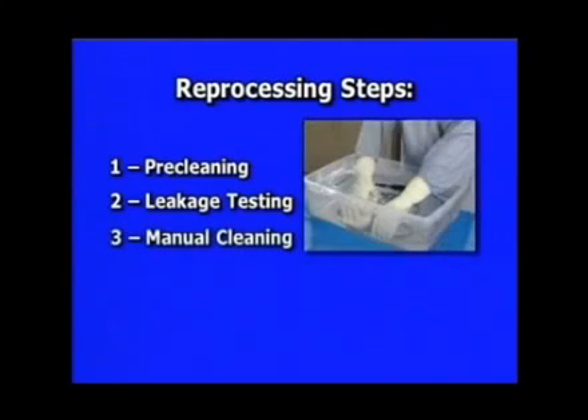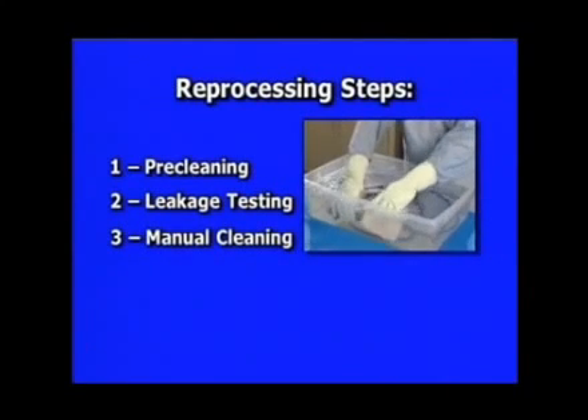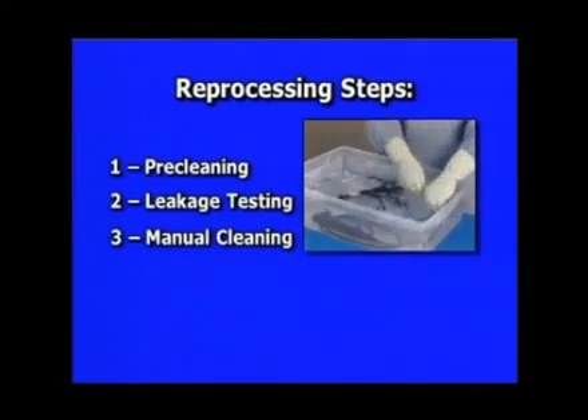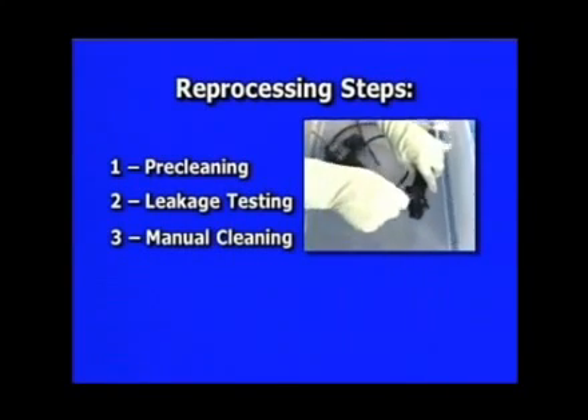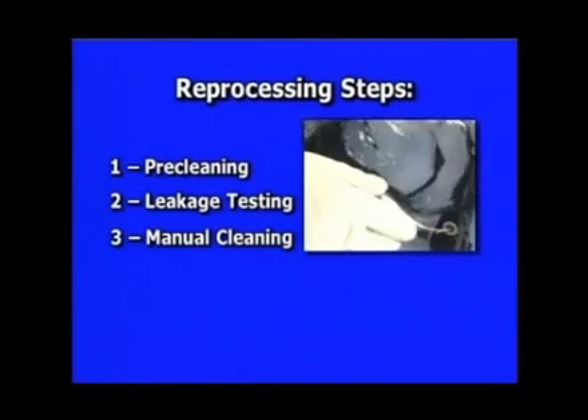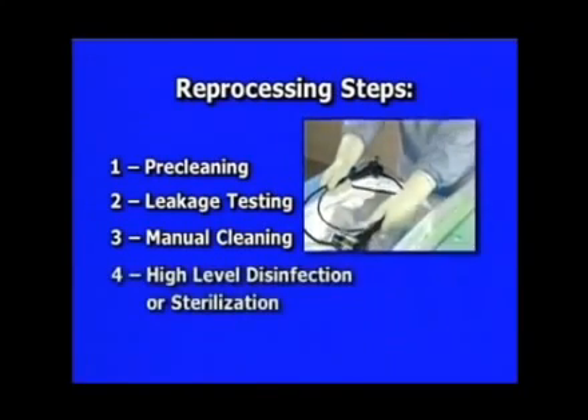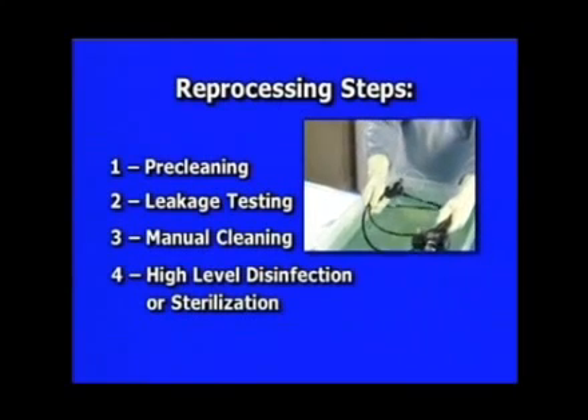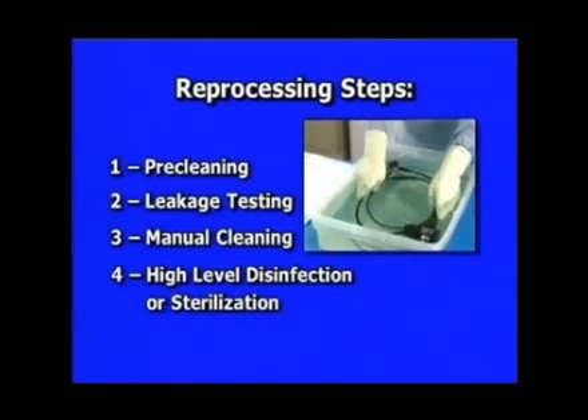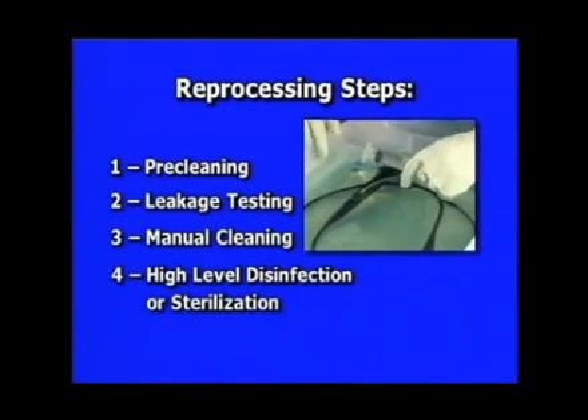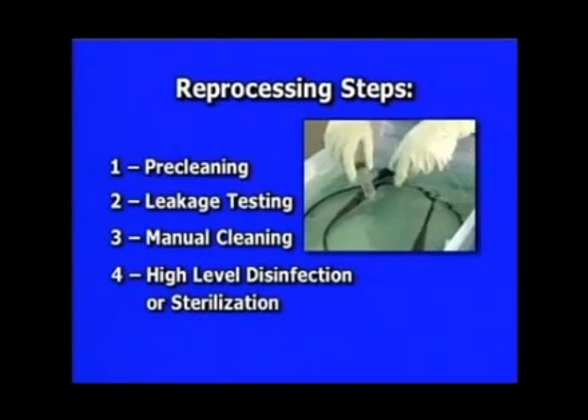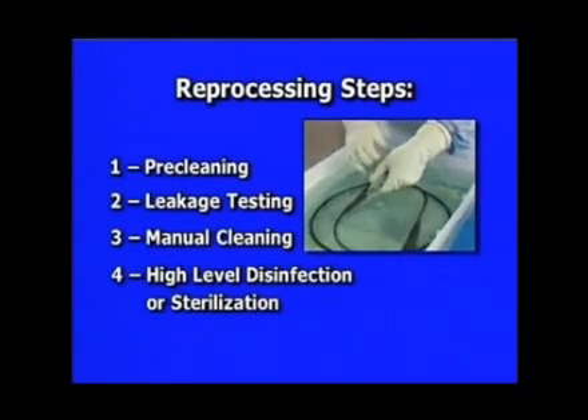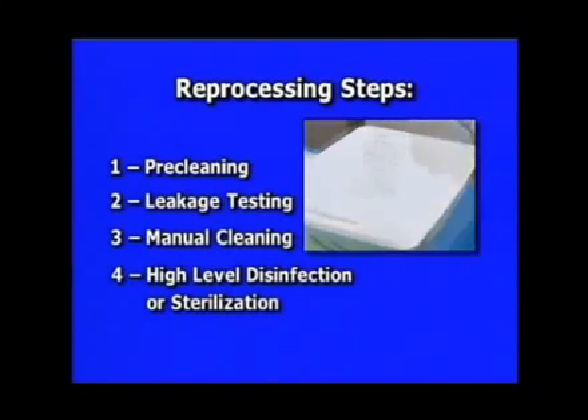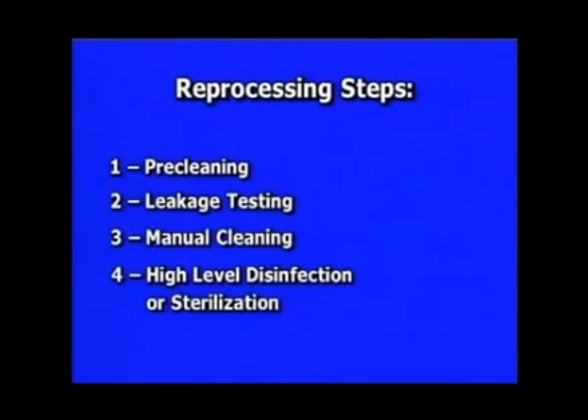The third step is manual cleaning. This involves thoroughly cleaning the exterior surface, all internal lumens of the endoscope, and all removable parts by wiping, flushing, brushing, and rinsing all surfaces. The final step is high-level disinfection or sterilization. High-level disinfection is performed by immersing the bronchoscope in an FDA-cleared high-level disinfectant and ensuring that all surfaces are contacted for the specified time and at the temperature recommended by the disinfectant manufacturer. As an alternative to chemical disinfection, the bronchoscope may be sterilized using an approved method indicated in the reprocessing manual.